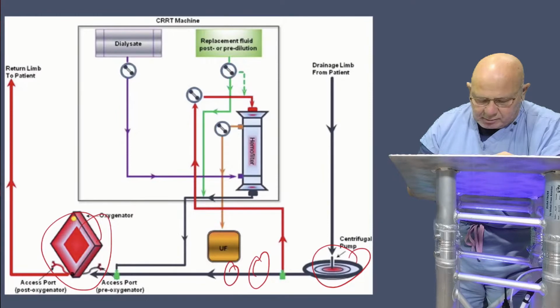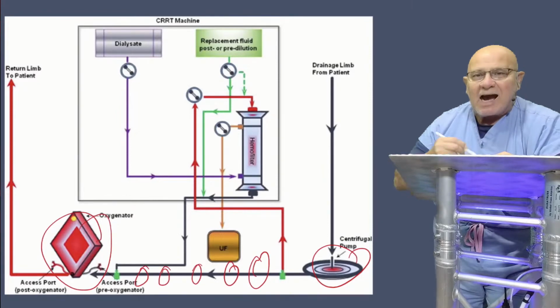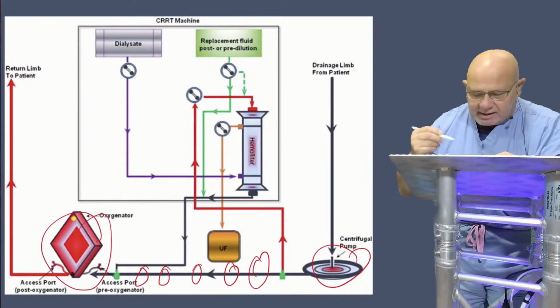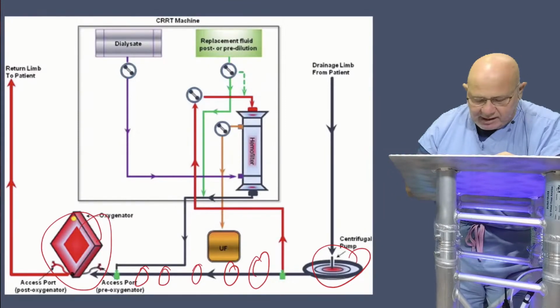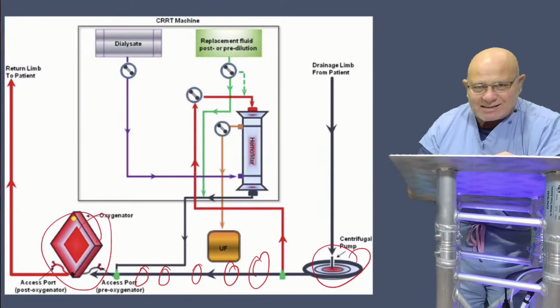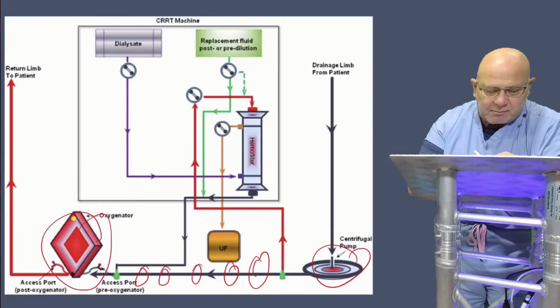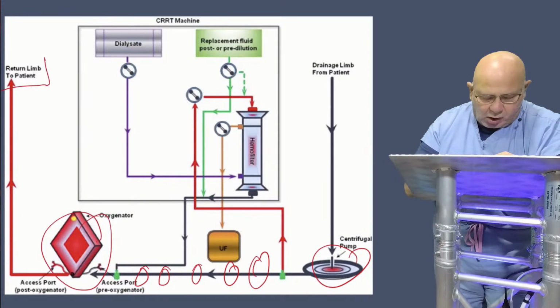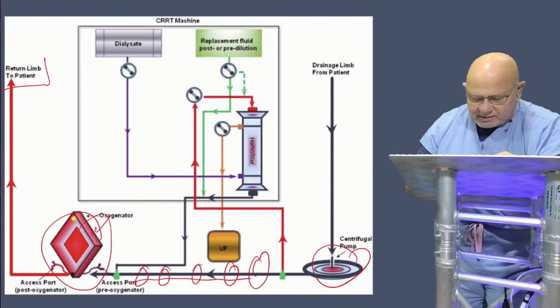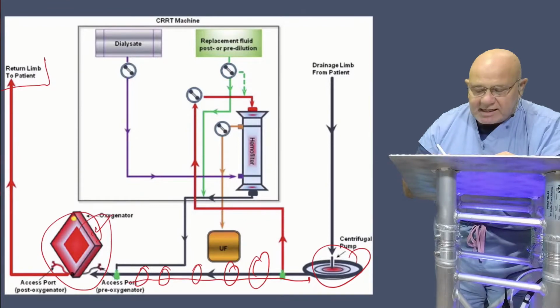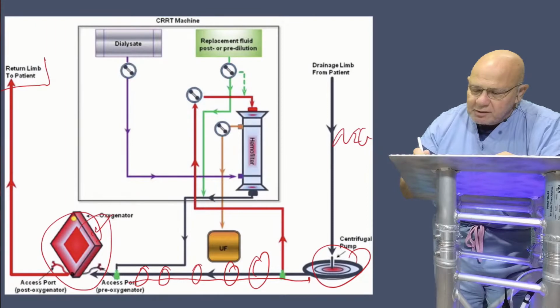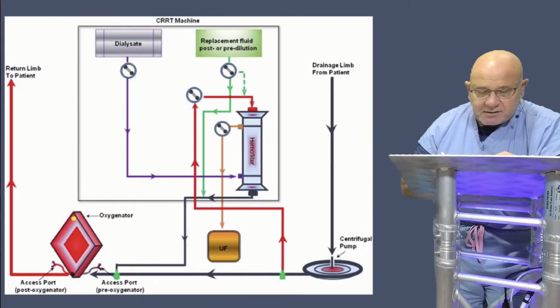This line right here is the line with the highest pressure in the entire circuit. So that is where your greatest amount of resistance is met, because again, you have the resistance from the return limb cannula all the way back through the oxygenator, the increased resistance there. So this line has your highest resistance in the circuit. This, of course, is negative, just like in the CRRT machine. So if you look at what they're doing, they're taking off of this very high pressure line with their access. Remember, red is access in a CRRT machine.